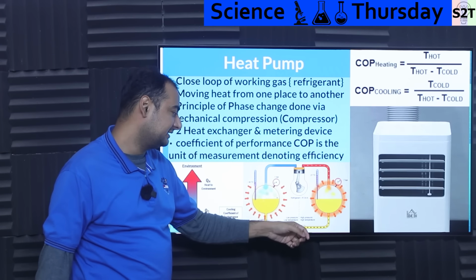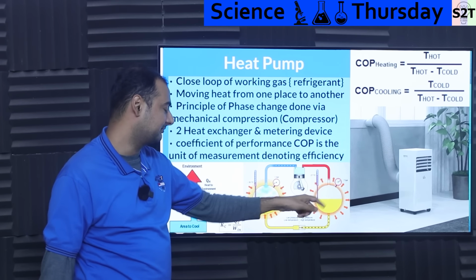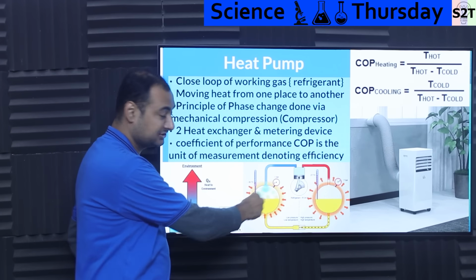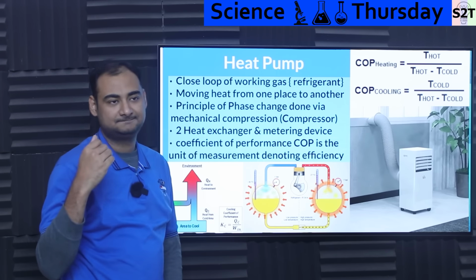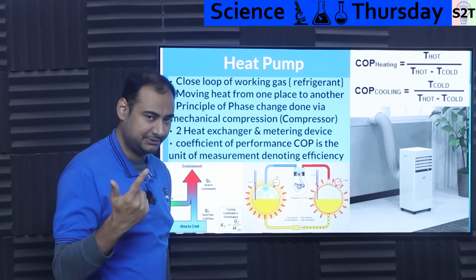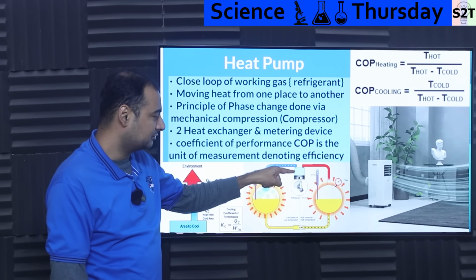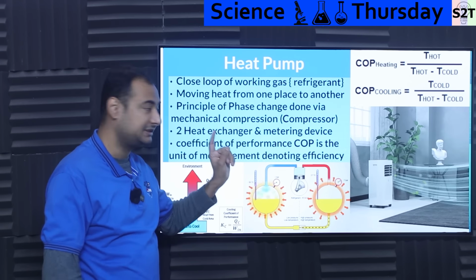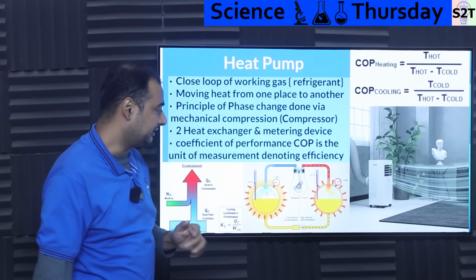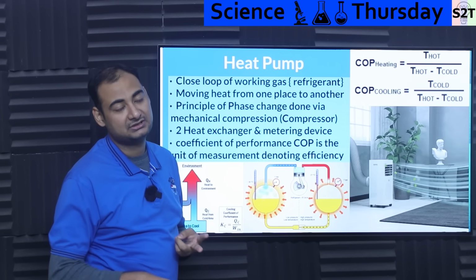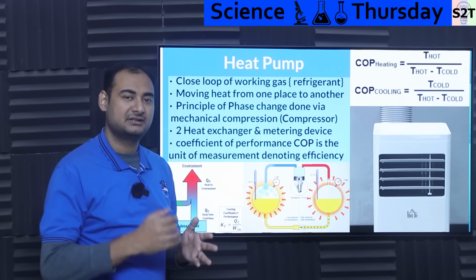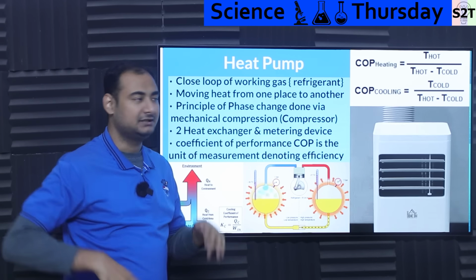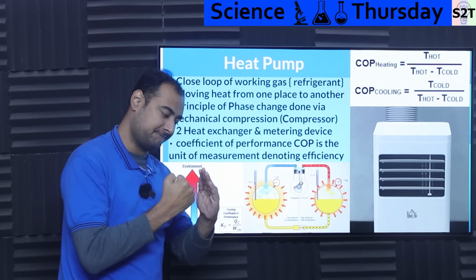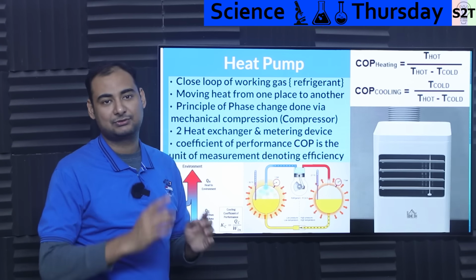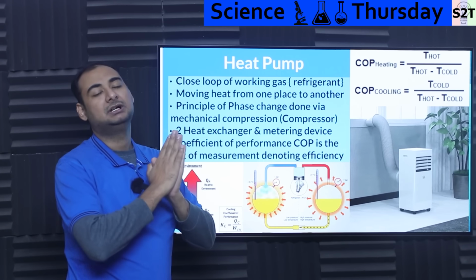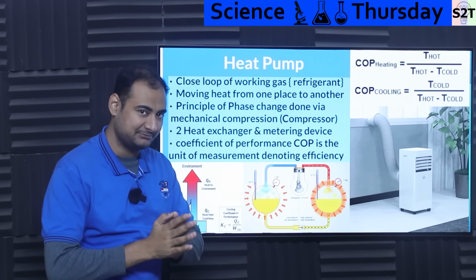Now here's the deal - boiling means you are consuming energy and you get into what we call low pressure, low temperature vapor. That vapor goes into your compressor. Now, the compressor in this scenario is a mechanical compressor - it could be rotary, piston, or scroll compressor, but generally it's a mechanical device; you're not doing any reaction, you're just compressing it. At that point, you go from low pressure vapor to high pressure, high temperature vapor.